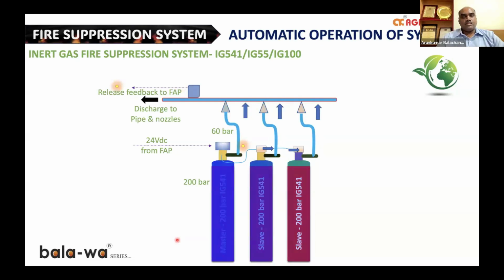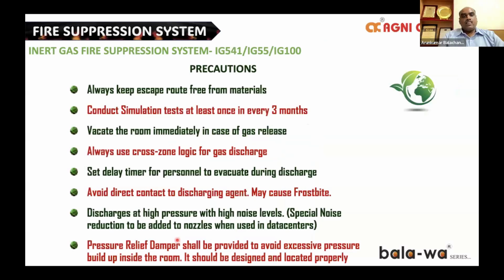Some precautions need to be taken care of. Always keep escape routes free from materials. We need to conduct a simulation test at least once in 3 months. Of course, we need to vacate the room. Even if it's an inert gas, we need to vacate the room. Always use cross-zone logic for gas discharge. Don't depend on just one detector for discharge, because sometimes it may lead to a false discharge. Set a delay timer for personnel to evacuate during discharge if it is possible.